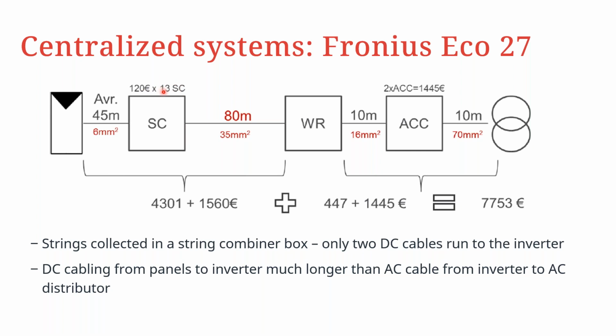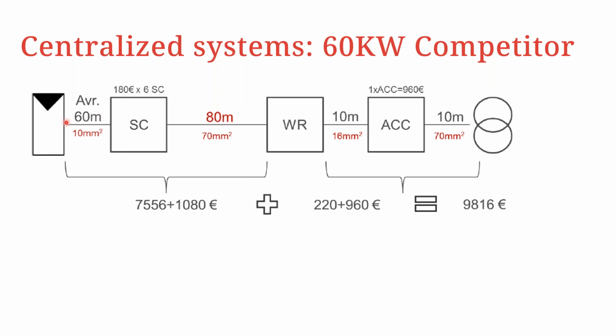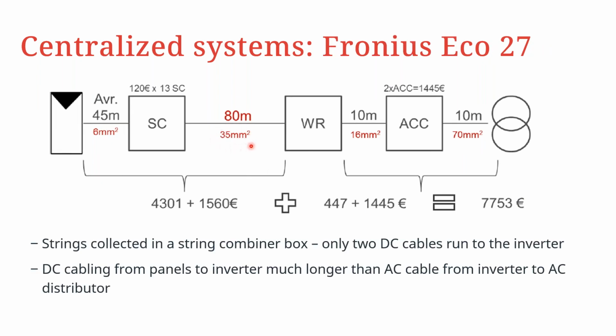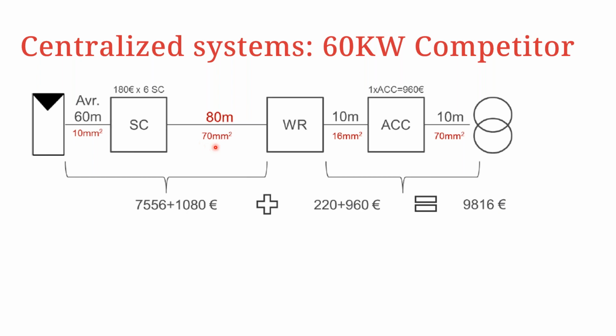Previously, for the Eco 27, 13 were needed. But then an important difference here is in the average distance. In this case it's 45 meters, but for this it's 60 meters. And then the cross-sectional area of the cable implemented: for the Fronius it was 35 mm squared, and for the 60 kilowatt competitor, it's 70 mm squared.